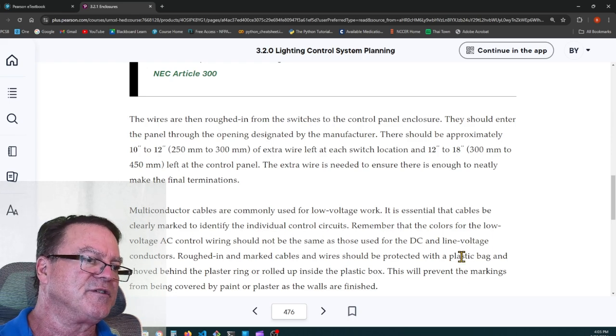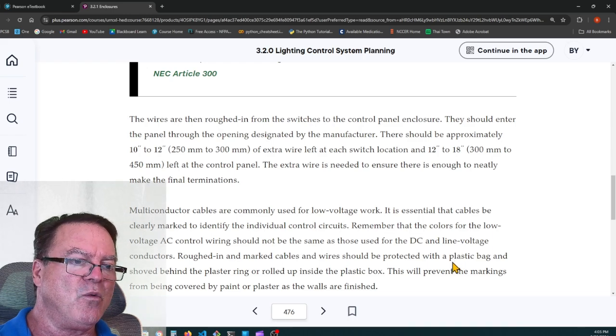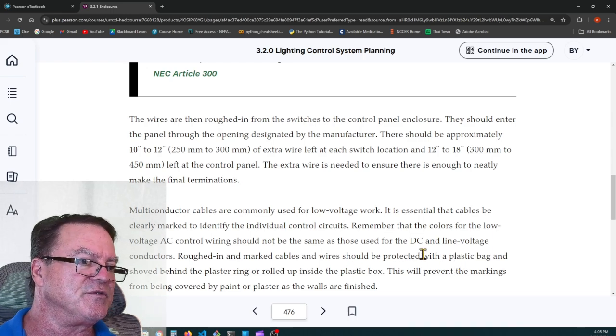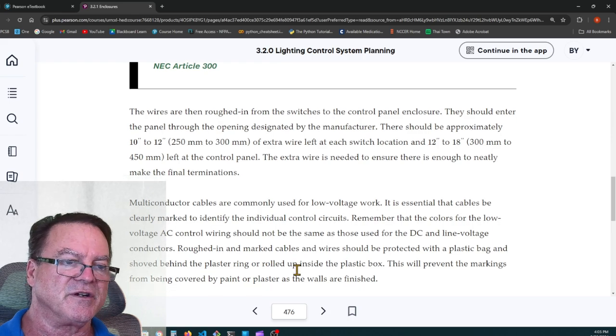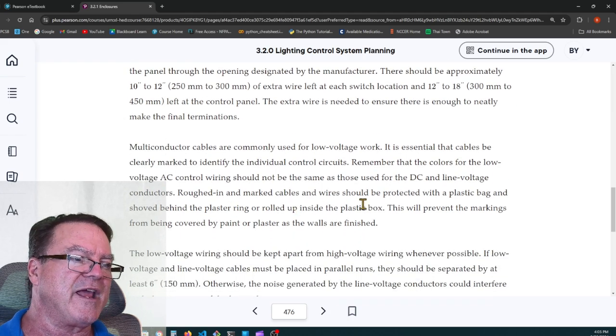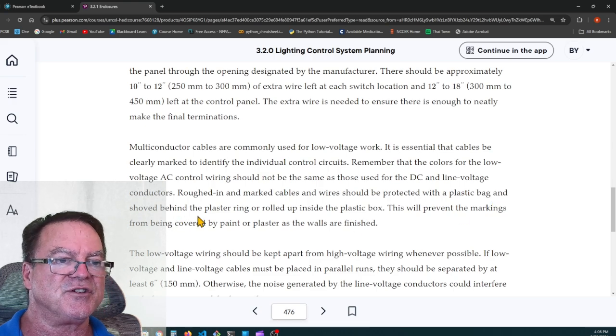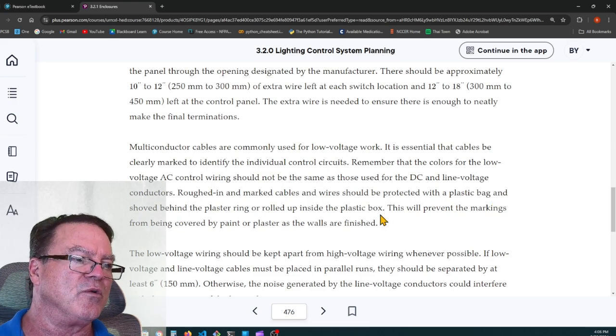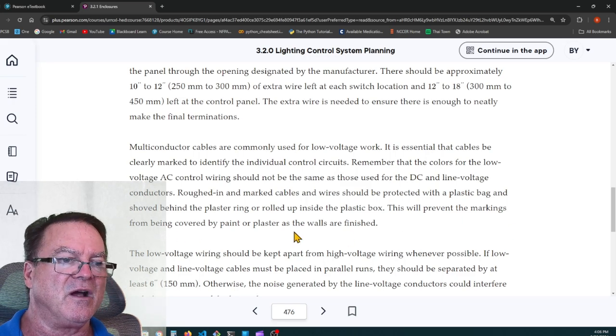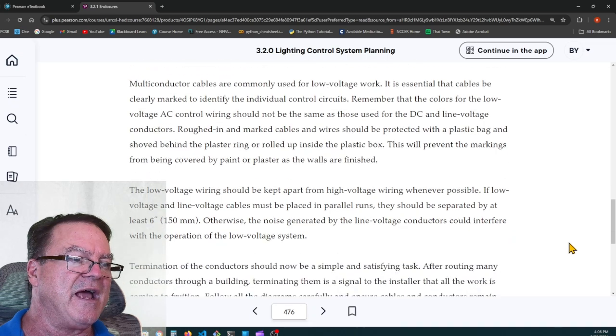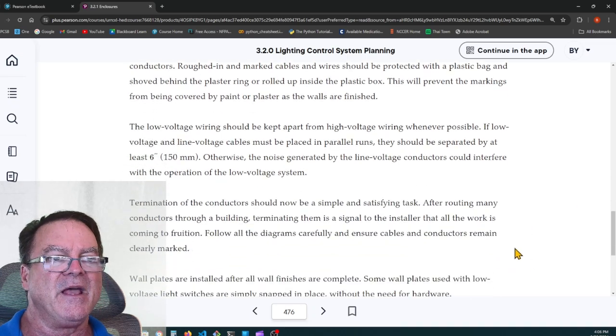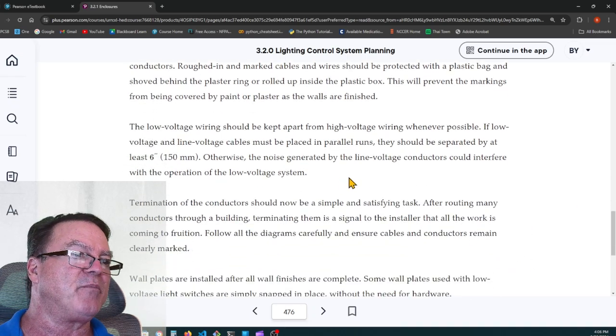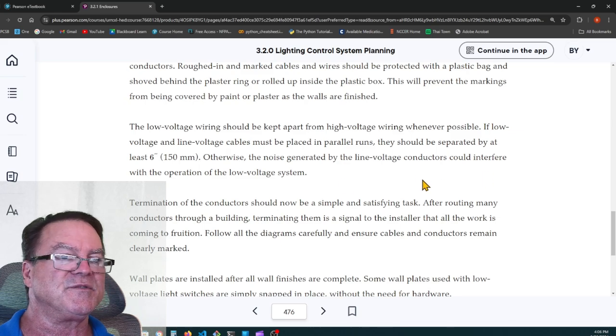Remember that the colors of the low voltage AC control wiring should not be the same as those used for the DC and line voltage conductors. Roughed in and marked cables and wires should be protected with a plastic bag and shoved behind the plaster ring or rolled up inside the plastic box. This will prevent the markings from being covered over by paint or plaster as the walls are being finished. The low voltage wiring should be kept apart from the high voltage wiring whenever possible.